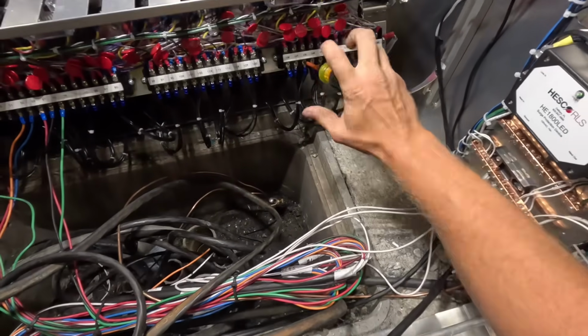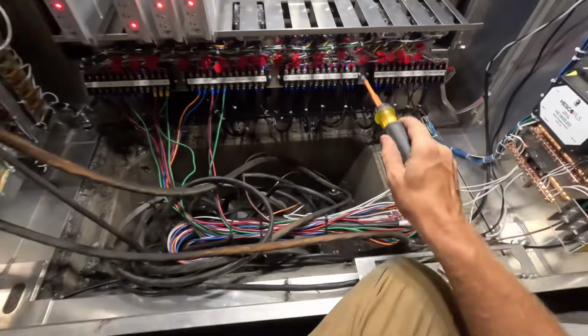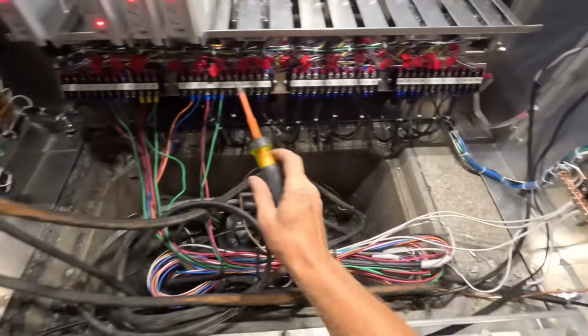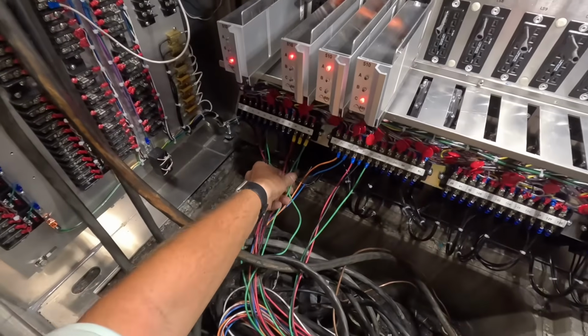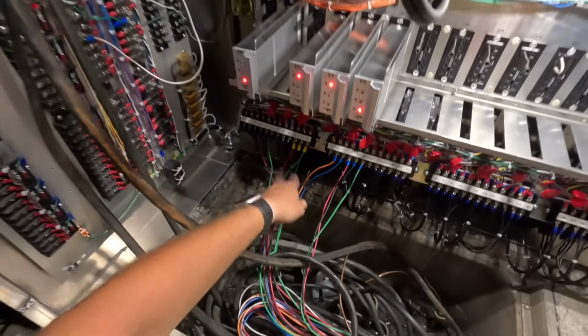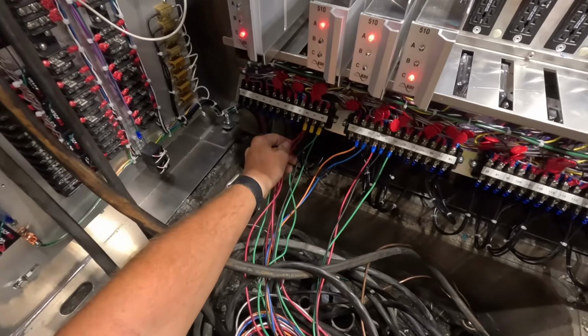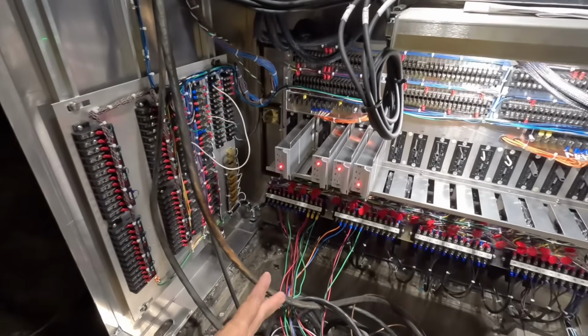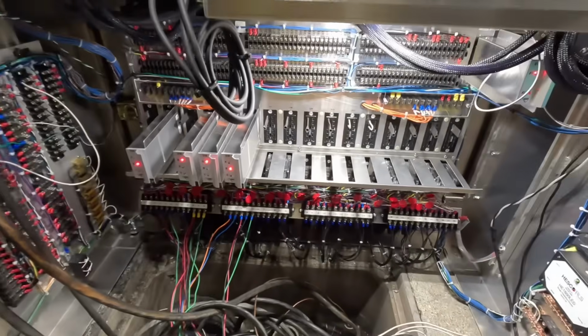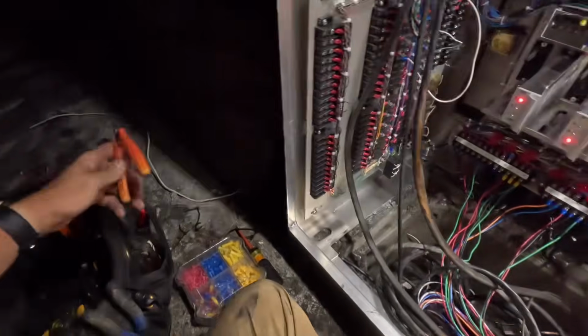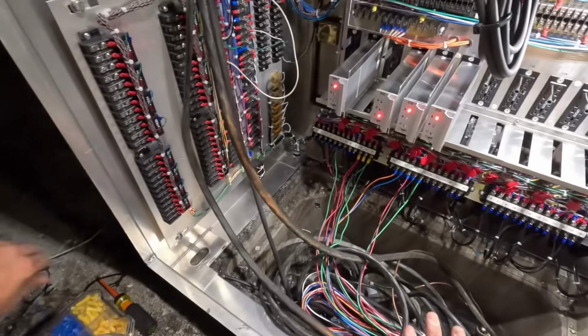I will have to change the flash pattern too. On there, I'm just gonna change it to red. So I'm gonna do a big pet peeve of my own, but I don't want the intersection going into flash necessarily. So I'm gonna cut these, and I may, when I have a good moment, pull those, restrip it real quick, and re-land it. But for the time being, to get everything set up, I'm gonna move some cables around. We gotta rewire this whole thing anyways. But stay tuned with me as we do this.